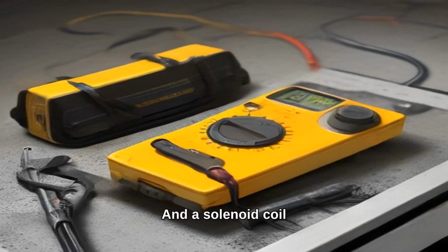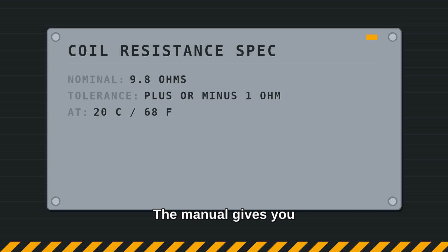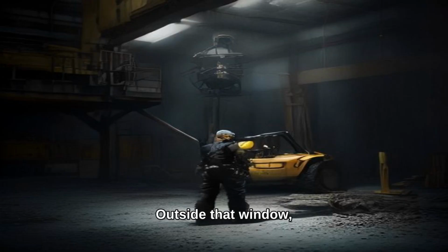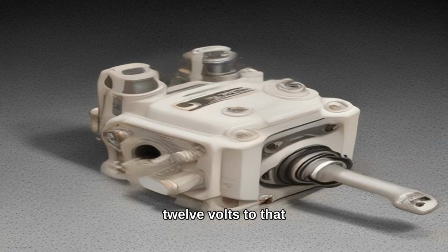And a solenoid coil is one of the few things you can actually test with cheap tools in the yard. The manual gives you the number. Coil resistance is 9.8 plus or minus 1 ohm at 20 degrees Celsius. Outside that window, the coil's your suspect. Inside it, stop blaming the coil and go back to the wiring. You can also put 12 volts to that coil. You'll see it move and you'll hear it.